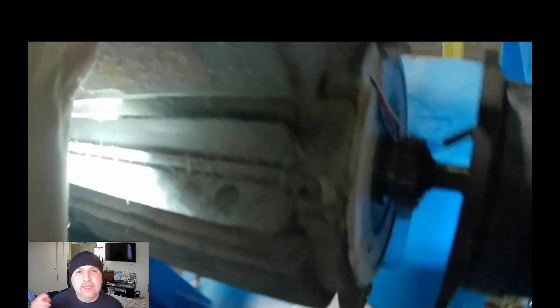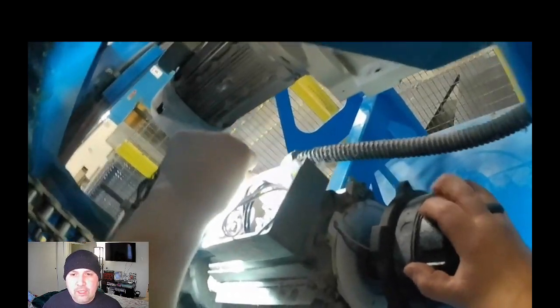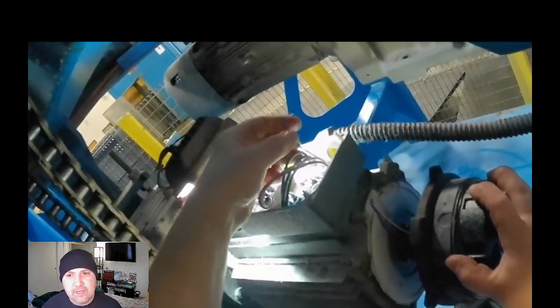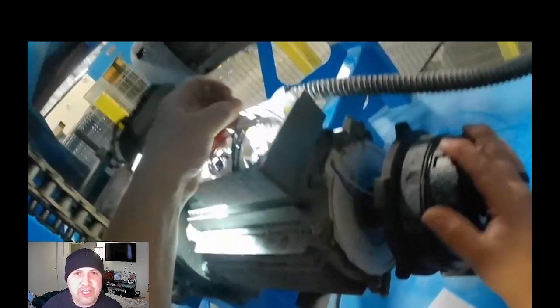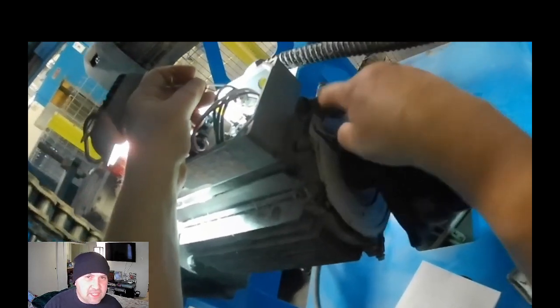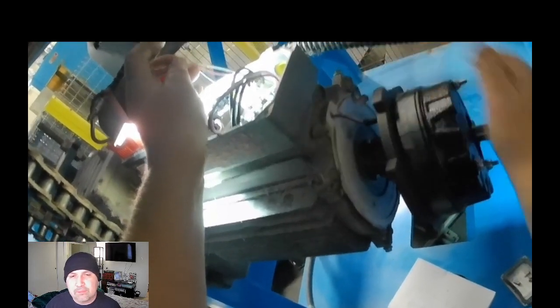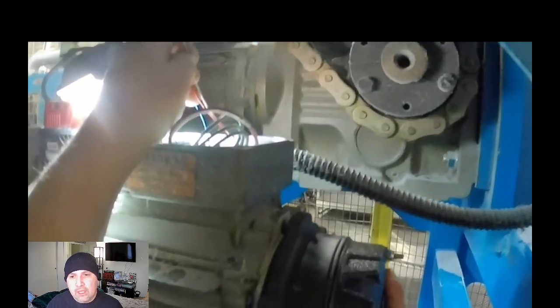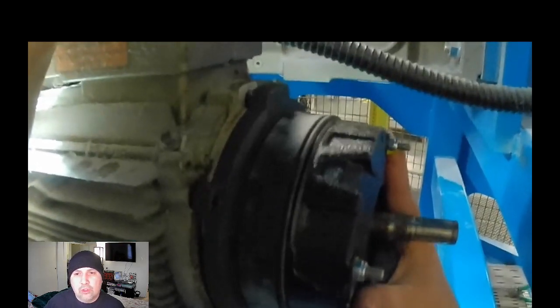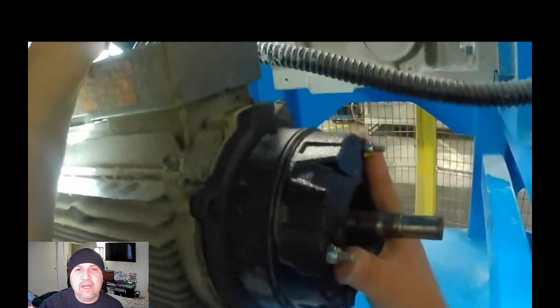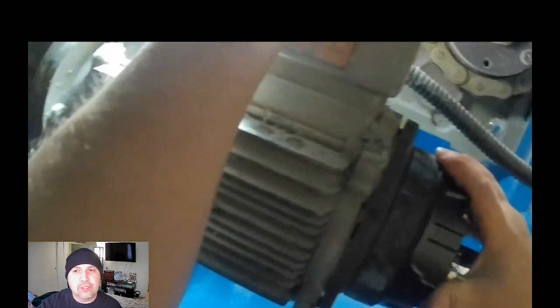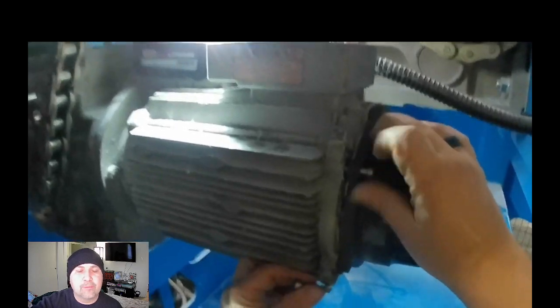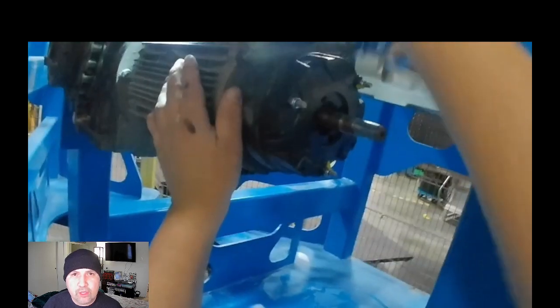So luckily they had another brake in their inventory, but I needed a concrete answer to give them. I couldn't just say, hey, let's start changing parts and see if it's this, let's see if it's that. I really wanted something concrete to tell them, and I was able to grab a brand new relay, put it in, and then I finally got voltage out there at the brake on the motor, in the little panel on the motor. I noticed that I was feeding the brake the 120 volts that it needs to operate, and it still wasn't operating.